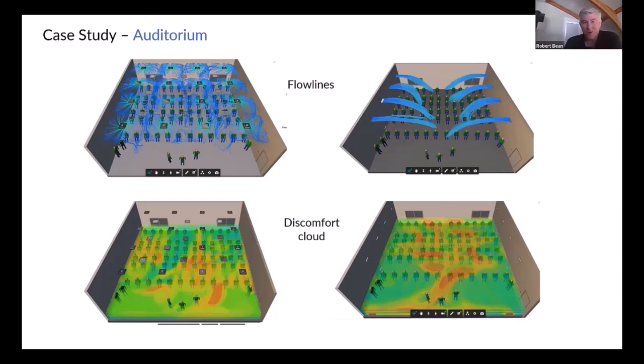I'm down in Arizona, minus 40 degrees up in Calgary. I'm down in the south hiding from the cold. And I get a call from the client. Andy was his name. And Andy said to me, he said, Robert, at minus 40, your original design was to be able to heat this space with 105 degree Fahrenheit water temperatures. And we're at design conditions and we're completely comfortable. Like nobody's complaining about cold, none of that stuff. And we want to drop the temperature down to see how low we can go.